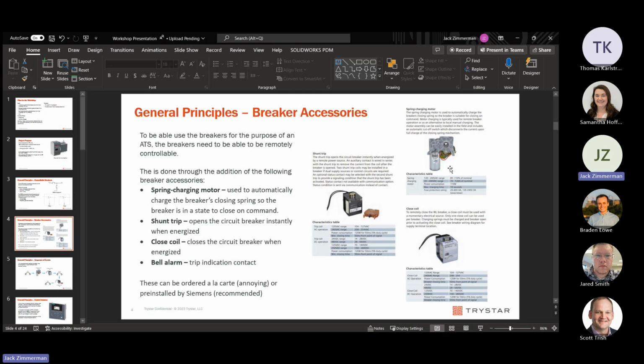As well as that, the bell alarm. So the bell alarm is just a contact that opens or closes based on if the breaker is in a tripped state. And all of this is doing in our case is telling the controller basically, hey, if the breaker tripped, it's not opened by the control system. If it tripped because of overcurrent, do not try to open or close the breaker again. Leave it in its state, because in a trip condition, we don't want the controller to keep trying to close it into fault conditions. That's a really important point.